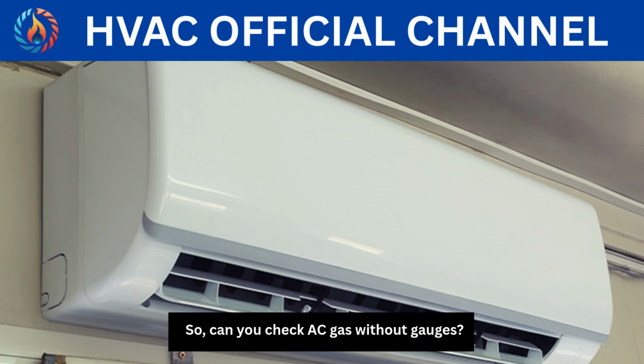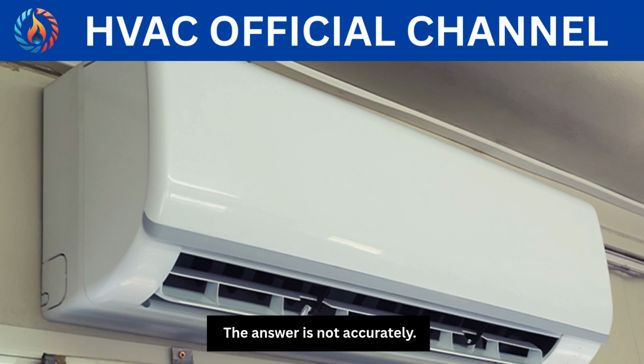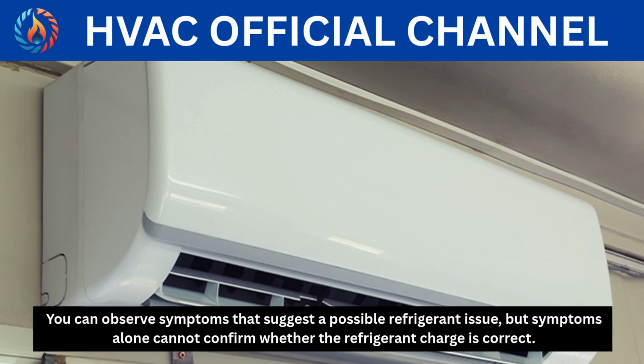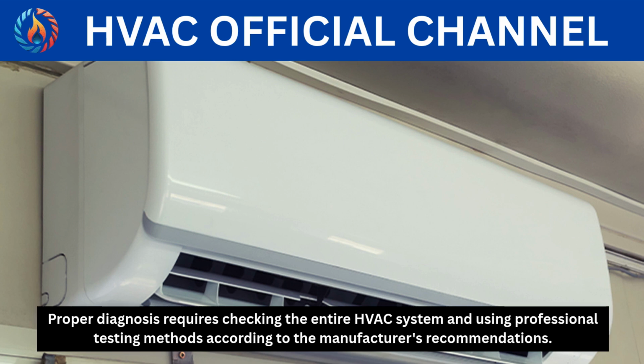Conclusion. So, can you check AC gas without gauges? The answer is, not accurately. You can observe symptoms that suggest a possible refrigerant issue, but symptoms alone cannot confirm whether the refrigerant charge is correct. Proper diagnosis requires checking the entire HVAC system and using professional testing methods according to the manufacturer's recommendations.